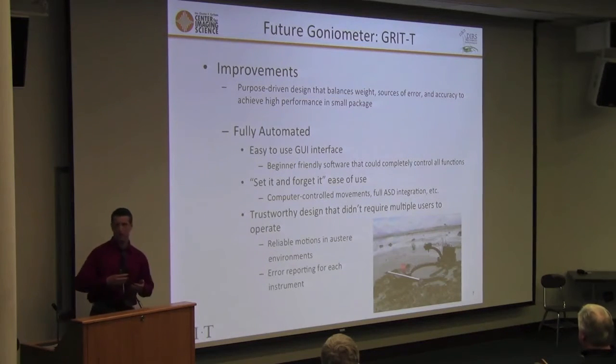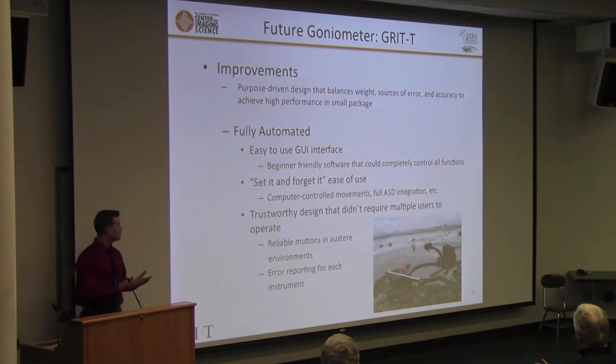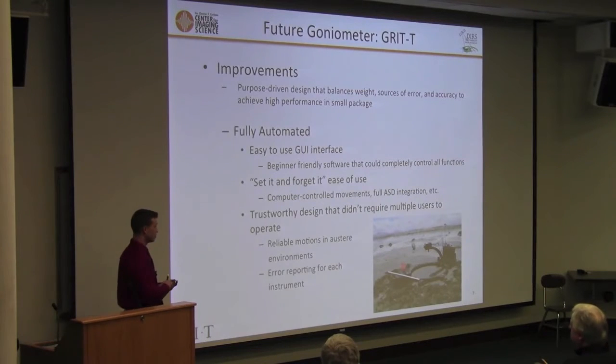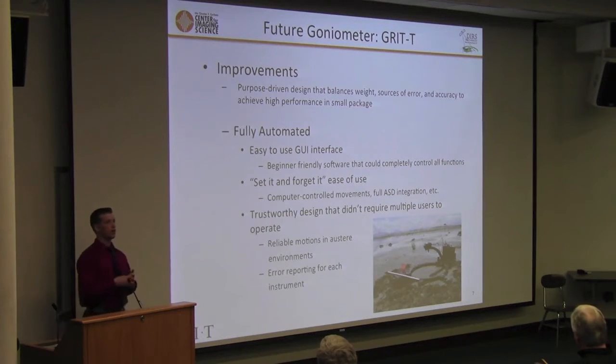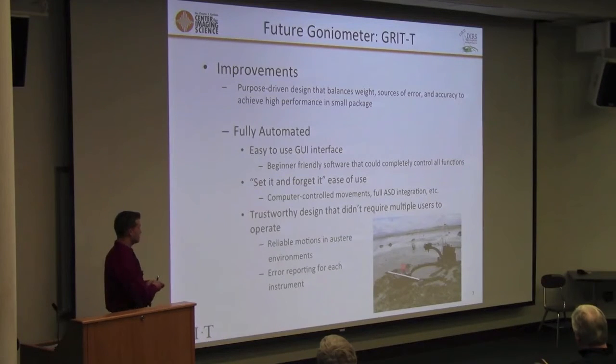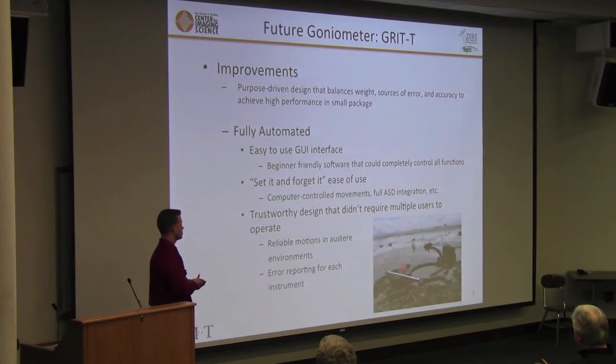You program your scan pattern in. The scan pattern is then executed automatically via computer-controlled motions that are constantly monitoring for errors and other things, and controlling the ASDs, all in conjunction. In order to do that, you had to have a trustworthy design because we didn't want multiple operators to have to sit there and monitor it and ensure that it's reaching where it's supposed to be going. So we required reliable motions in austere environments.